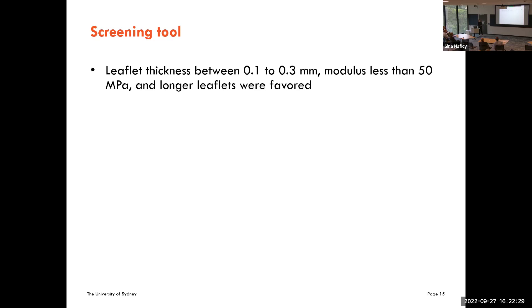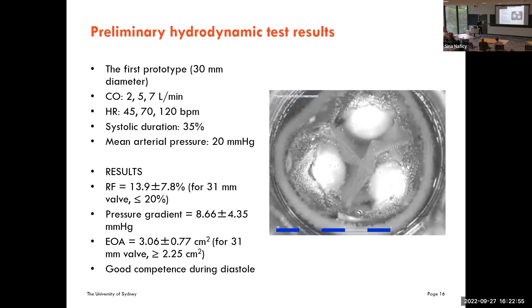From this screening study we determined that we need a leaflet thickness of up to about 0.3 mm, a Young's modulus of less than 50 MPa, and that longer leaflets are favored over shorter ones. However, there is a limit — leaflets that are too long produce unwanted twisting motion during the transition between closed and open positions.